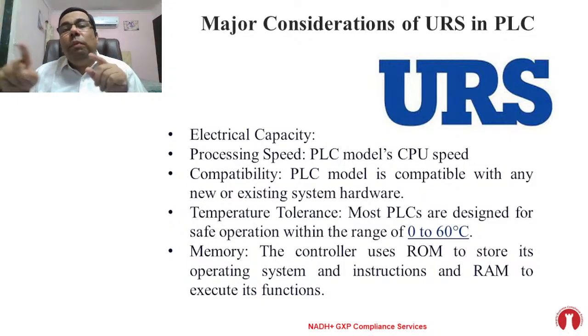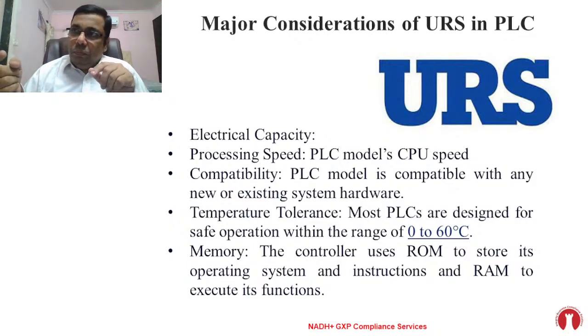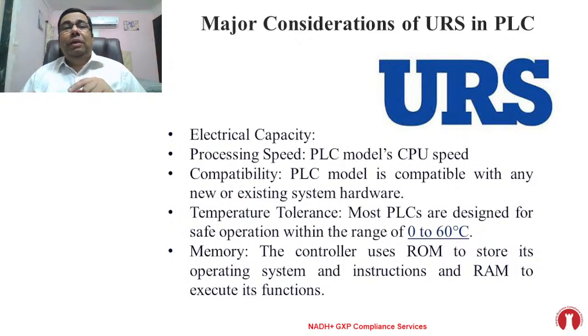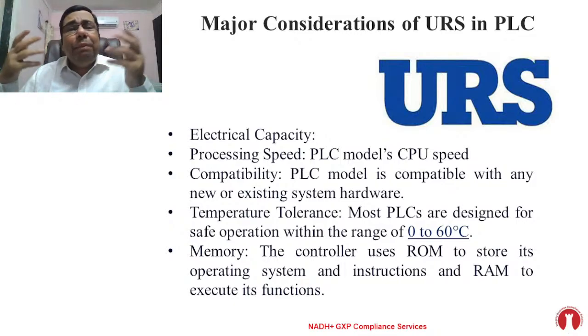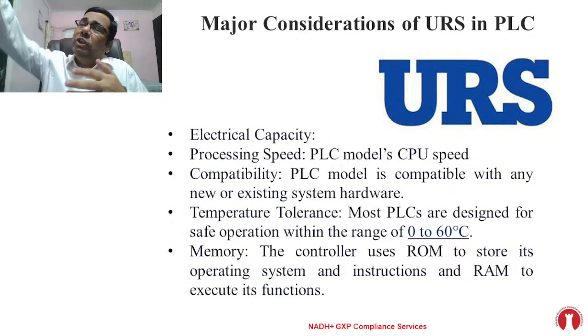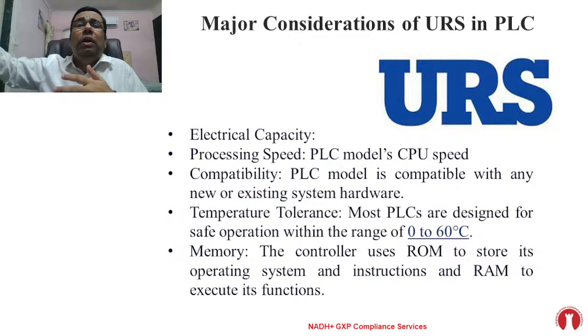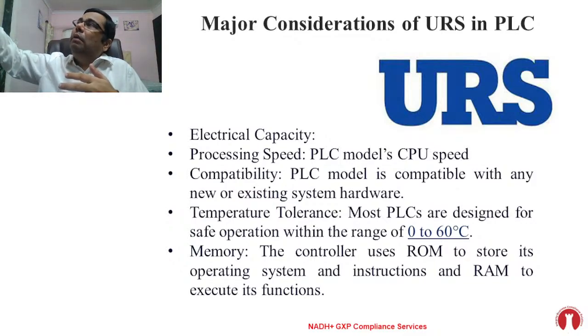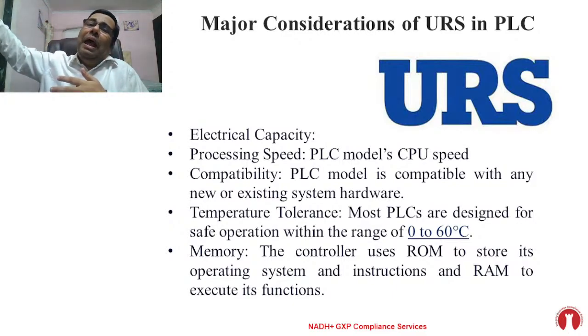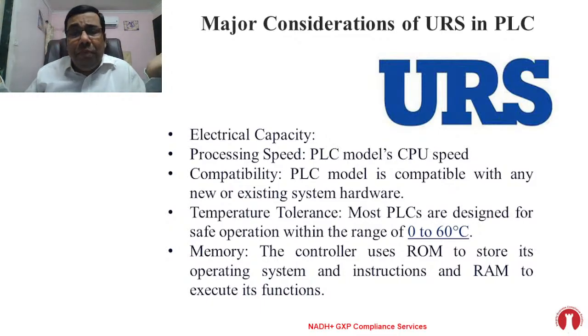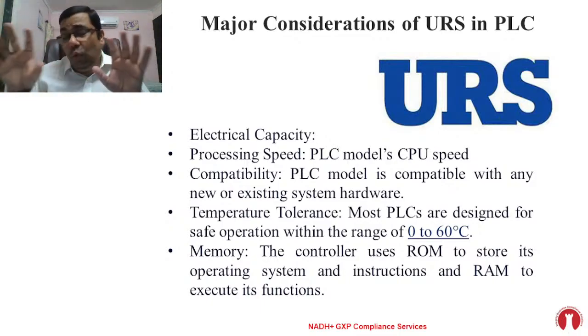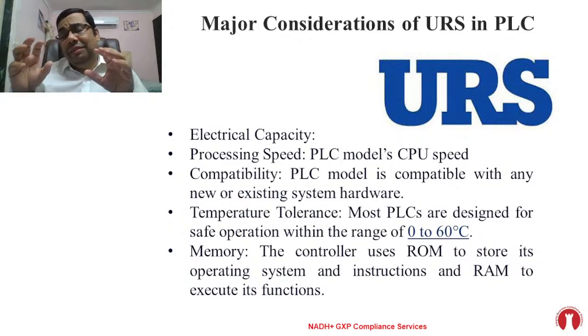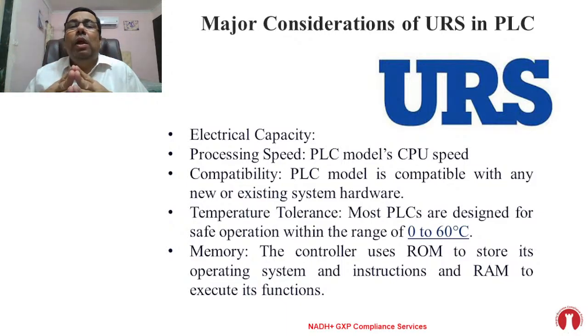So what is the CPU speed, what is the PLC model? Because if the output is required on an immediate basis but the speed is very low, then my purpose will not get solved. There will be a temperature excursion, for example, and the alarm will not be given because of a delay, and due to that some hazards may happen. I'm just giving examples to make you aware of how the URS should be built for the PLC.